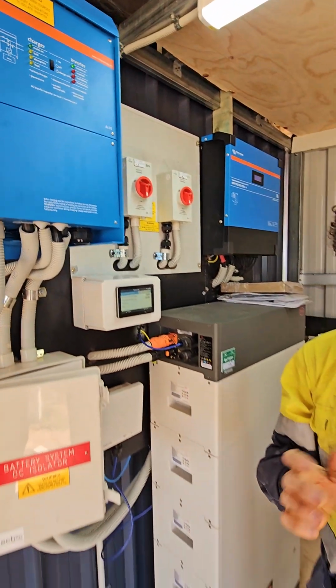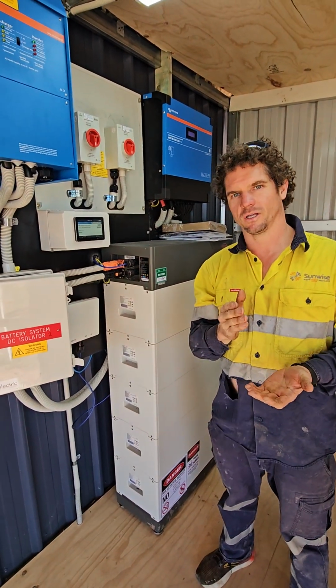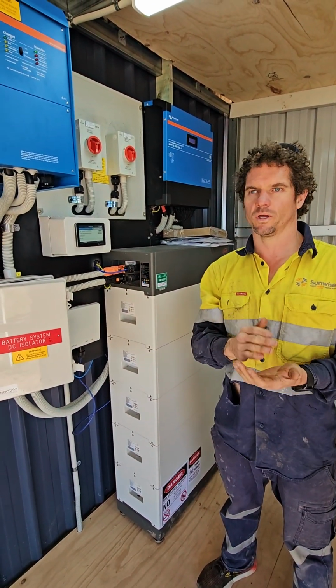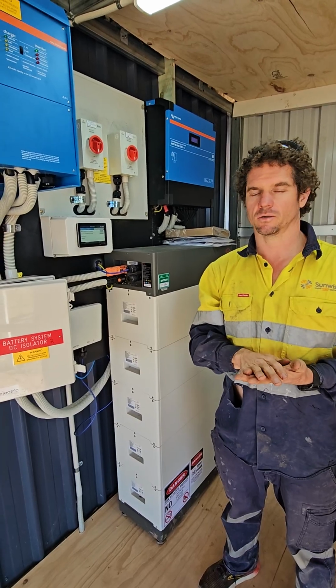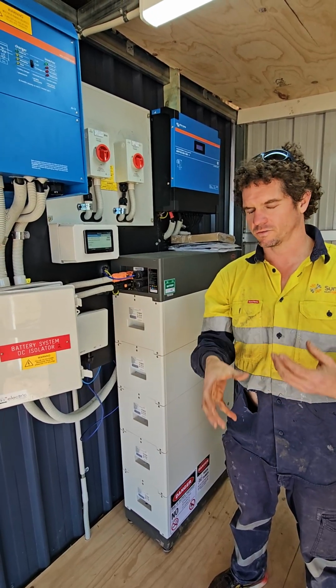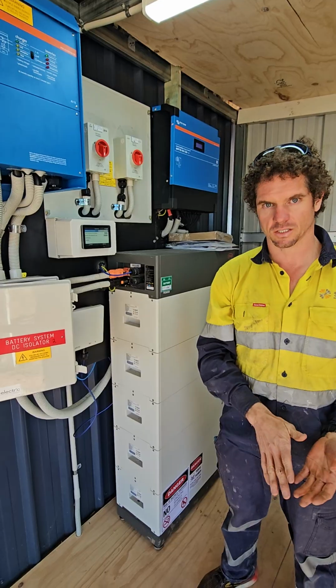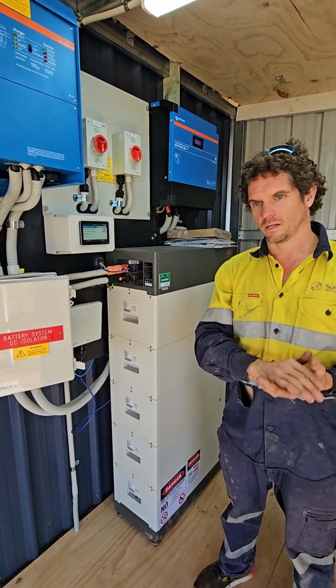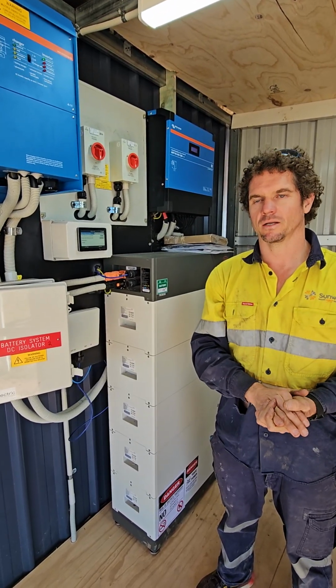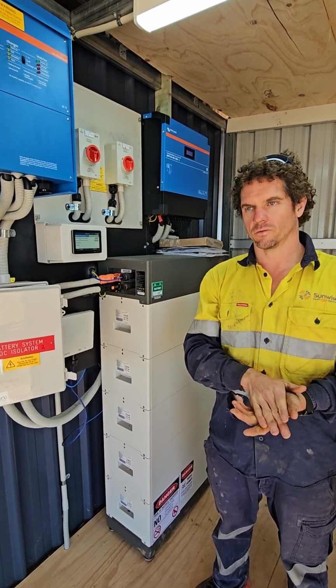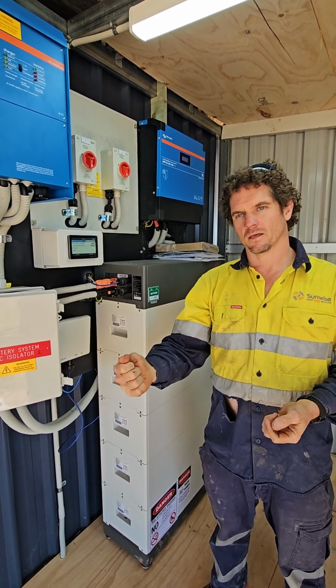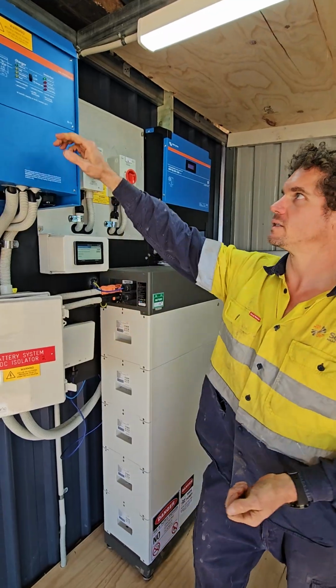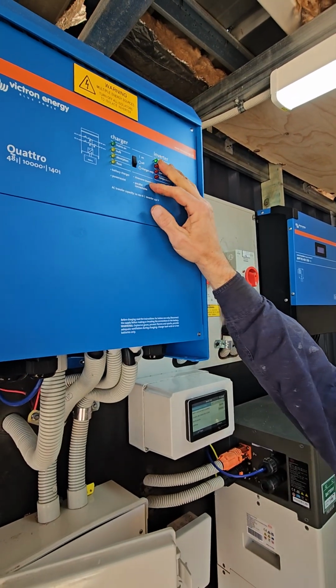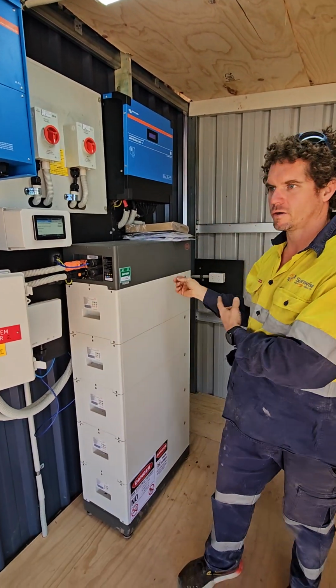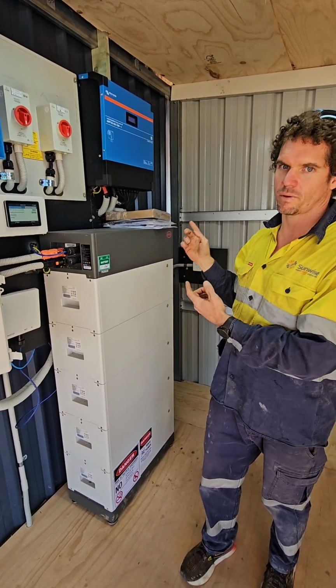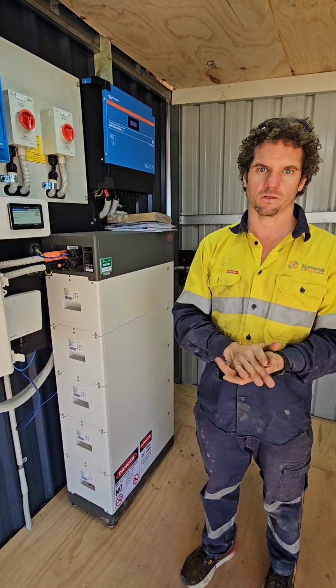You can use the charger only position on the Victron if there's been very little sunshine and the battery's gone flat, and for some reason the generator hasn't started, so you've deep discharged your battery down to a really low level and want to restart the system without having any load on the battery, so you can get some charge in before you put the loads on. Flick that down to the bottom, to charger only, manually start your generator, then go and start the system from the battery forward like we just went through.